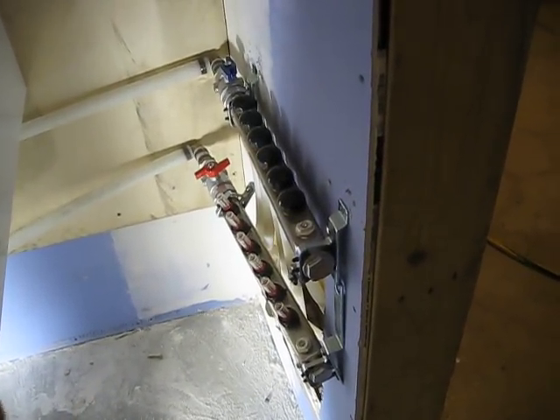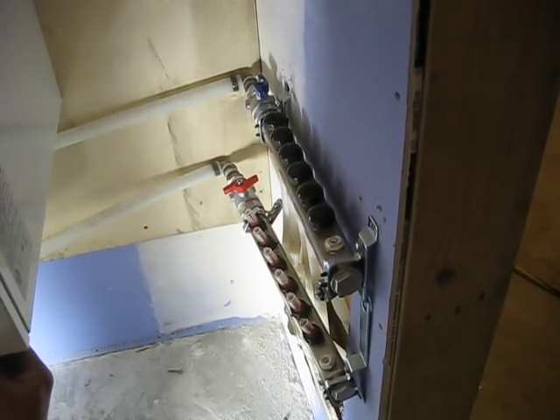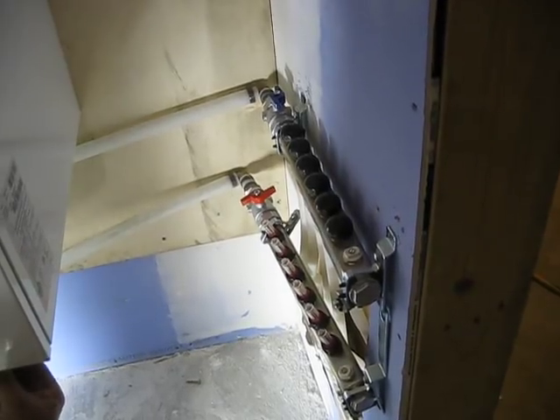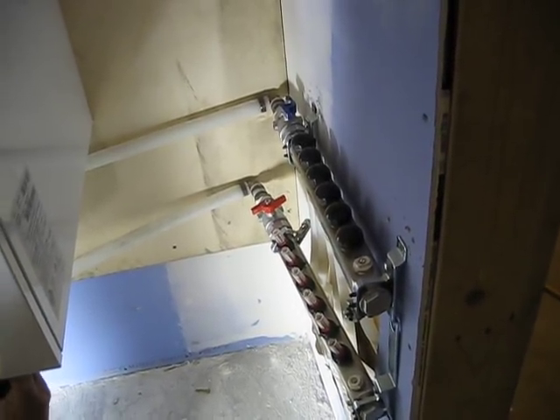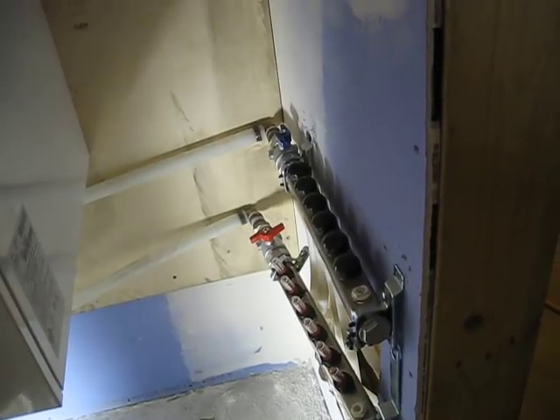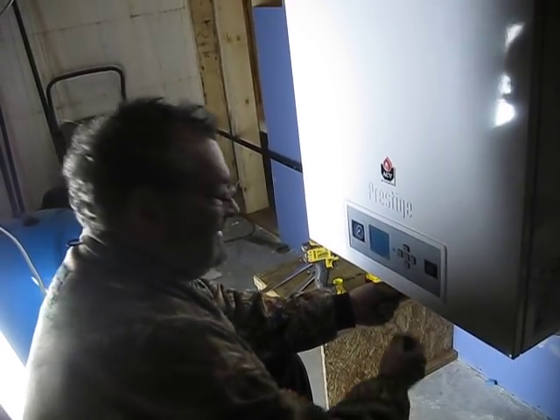Oh, okay. Now, we're going to fill this with glycol, so if you went away and the power went out, it wouldn't freeze up. You can stand for your plumbing to freeze up, it's hundreds or thousands. When your in-floor freezes up, it's tens of thousands. Well, it's in the concrete. Right, yeah. So what people do when it freezes up is they bring it up another inch and a half and put more pipe in it, and then shorten all your doors by an inch and a half. Oh, goodness.